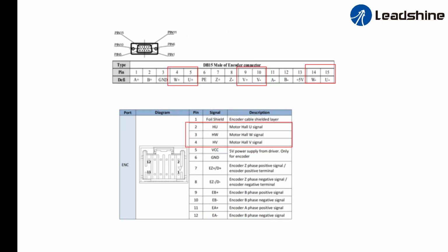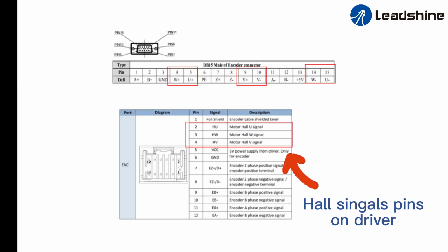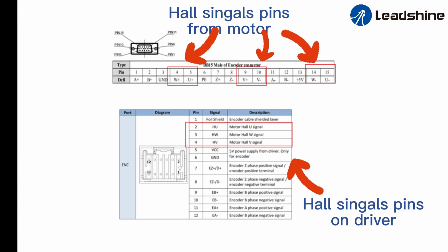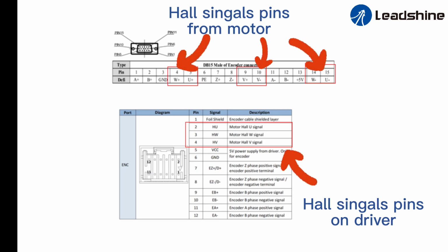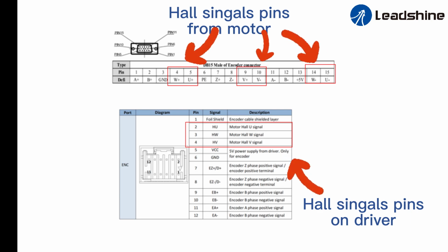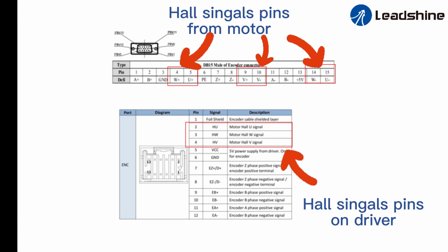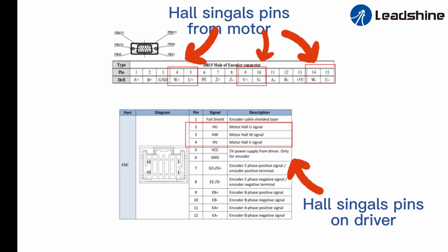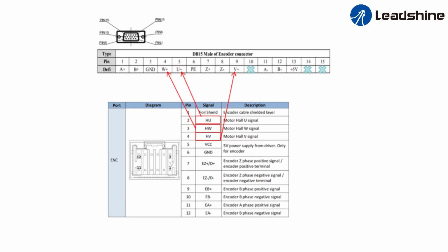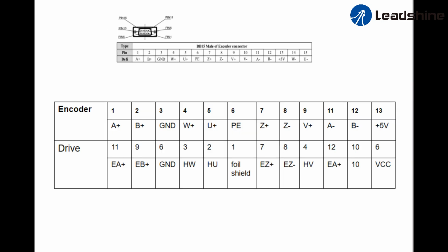As you see, for the Hall sensor signal, the drive has only HU, HW, and HV. However, the encoder connector includes W+, W-, U+, U-, V+, and V-. So we should ignore U-, W-, V- and connect U+ to HU, V+ to HV, and W+ to HW. And then we connect them according to these two graphs.